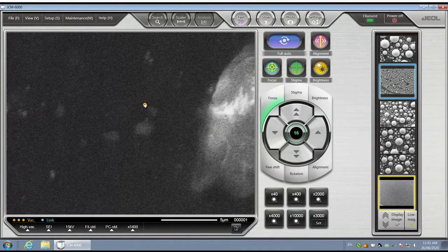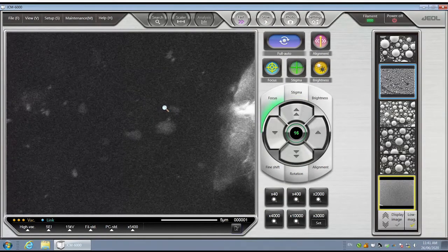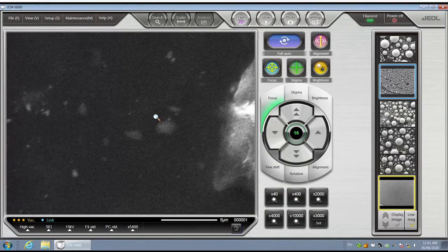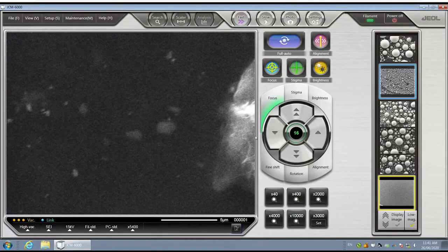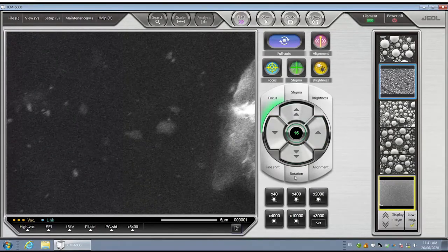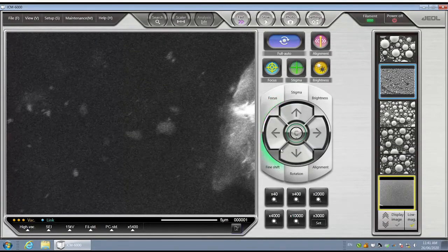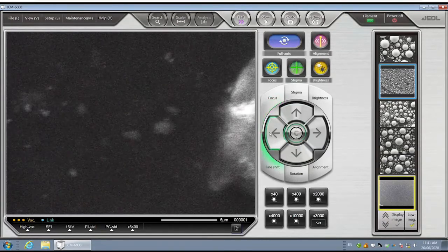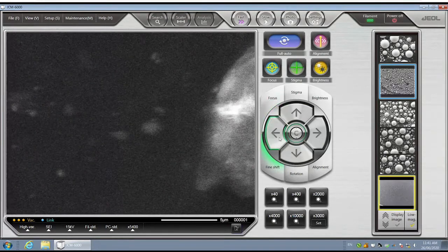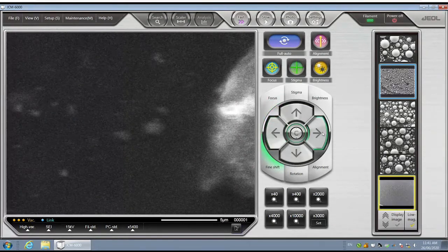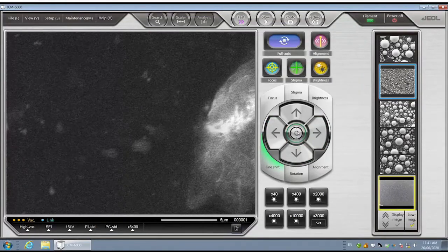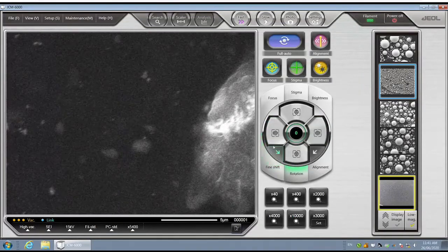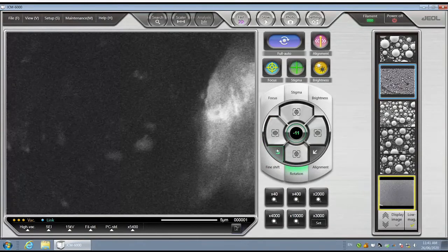Move to different areas or different samples using the X, Y, and rotation knobs. At high magnifications, moving the sample to get the right position may be hard. You can perform small beam shifts by left-clicking the image and dragging, or by selecting the fine shift button and clicking the corresponding directions, or select C to bring it back to center. You can also rotate the image by selecting the rotation button and pressing rotation options.